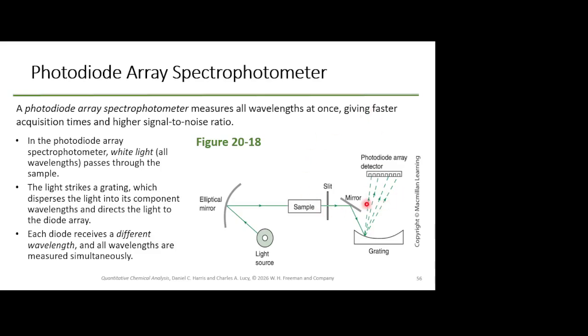All right. And so depending on which multiple of the wavelength you are, that's going to give you the different wavelengths that are detected by each of these detectors here. Now, note that again, this is one of the reasons why you have to run backgrounds, by the way, is that the amount this photodiode array detector actually detects each of those wavelengths may actually be a little bit different.